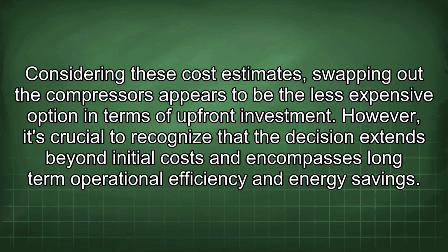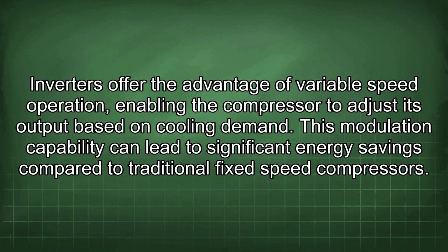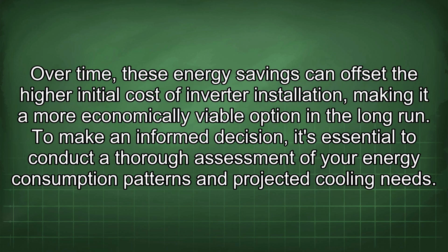However, it's crucial to recognize that the decision extends beyond initial costs and encompasses long-term operational efficiency and energy savings. Inverters offer the advantage of variable speed operation, enabling the compressor to adjust its output based on cooling demand. This modulation capability can lead to significant energy savings compared to traditional fixed-speed compressors. Over time, these energy savings can offset the higher initial cost of inverter installation, making it a more economically viable option in the long run.